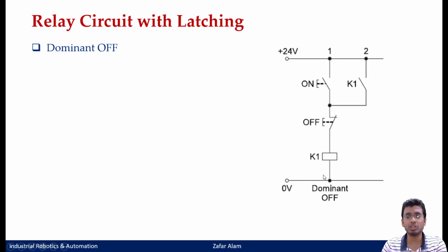Now just try to imagine, if you press the on push button, your relay K1 will get energized, and hence the open contact of this relay K1 will get closed, and you will have your K1 relay latched. If you press off, then the relay will become unlatched. However, if you press both on as well as off push button together, will the relay K1 energize and get locked, or will it not?